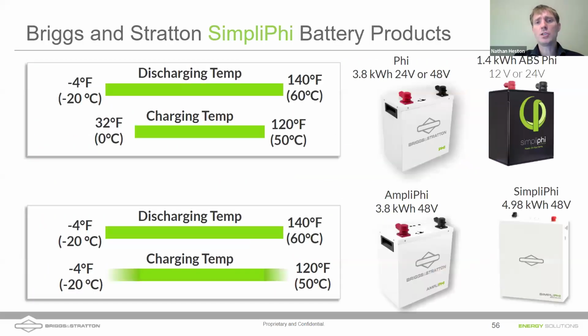Also, of course, you can use insulation, but for our non-communicating batteries, the ones with a simpler BMS, their operating range is from 32 Fahrenheit up to 120 Fahrenheit on the charging side, and on the discharging side, you can discharge them from -4 Fahrenheit, -20 Celsius, this is very cold, right, up to 140 Fahrenheit. When you're discharging the batteries at cold temperatures, it doesn't take long for the battery itself to warm up and for you to get more overall capacity, unless you're discharging very slowly in very cold temperatures. So keep these temperatures in mind. You are going to have to protect your batteries from charging below freezing in cold environments.